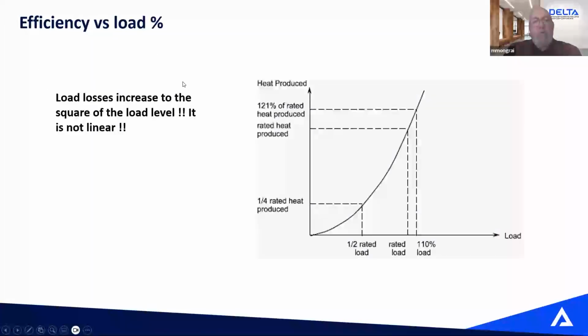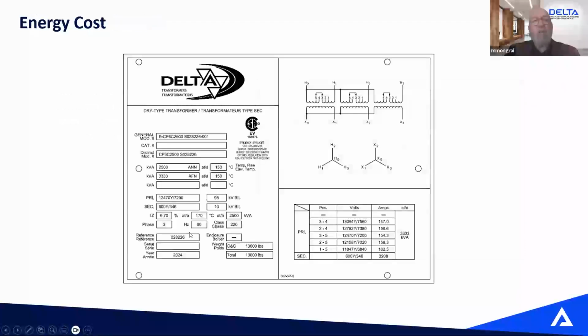In transformers, the efficiency is not linear. So the more you load a transformer, the less efficient it's going to be. You have two types of losses: the no load losses, the loss in the core that you're stuck with all the time, even if you have zero load, and then the load losses, the losses in your winding. But those losses increase with the square of the load. So at 50% load, you generate 25% of your load losses. So the more you load, the less efficient it's going to be.